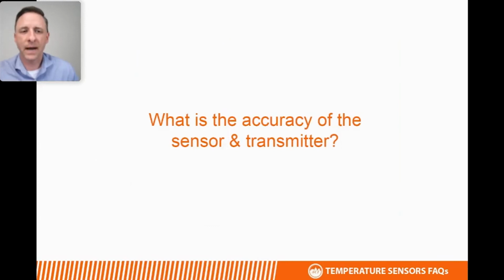What's the accuracy or the combined accuracy of the sensor and transmitter? It's very difficult to give a one-size-fits-all answer to this question because the different components of the device all have different levels of tolerances. The different temperatures in which they're operating can affect the accuracy of both the sensor and the transmitter. So I would refer you to the data sheet of the specific sensor that you're using, where the accuracy is called out. It's hard to give an overall accuracy due to the variability of the components used as well as the specific applications in which they're being used.